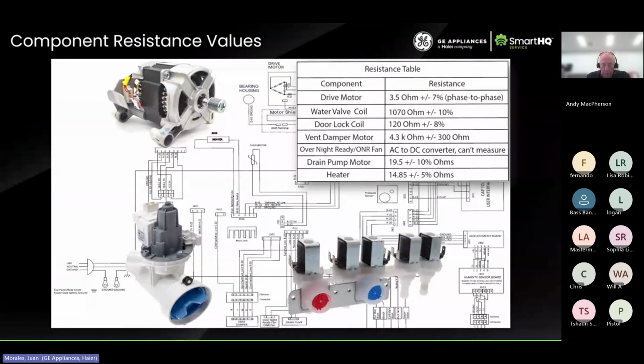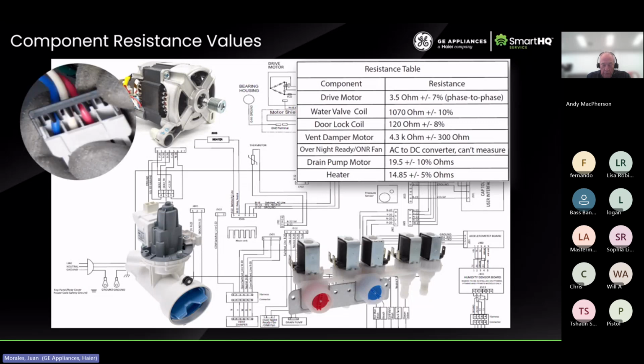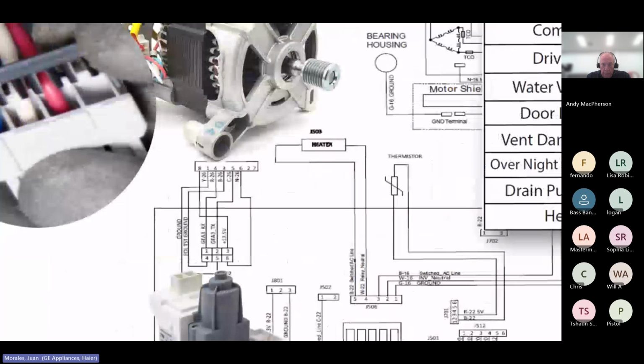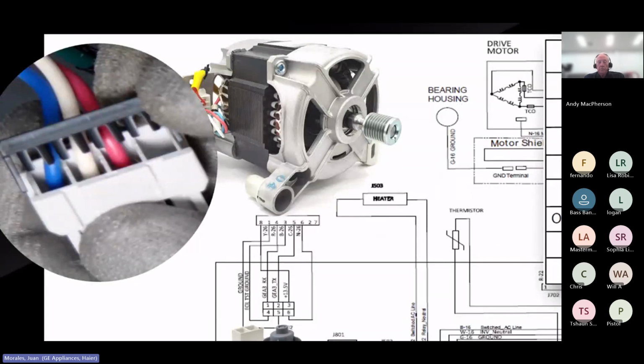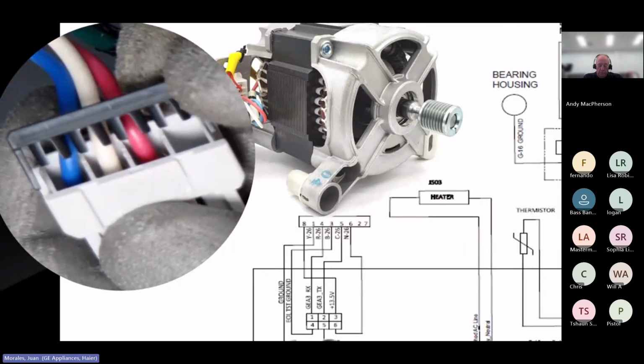Let's start with the inverter board connector, which is your motor. If I detach the motor connector from the inverter, I can measure between the blue and white, blue and red, or white and red wires, and I should get that 3.5 ohms we talked about earlier.